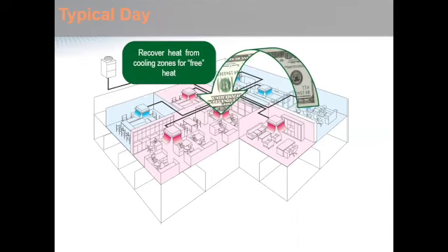So this is what we call free heat. That's a typical term you are going to hear when you deal with VRF in the HVAC marketplace. And this is typically a function of recovering all of that waste energy from the zones that are providing cooling and redirecting it through a BC controller, or a controller of some kind, into the zones requiring heating.